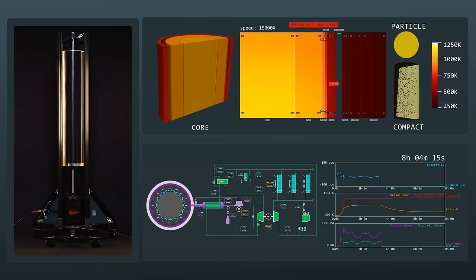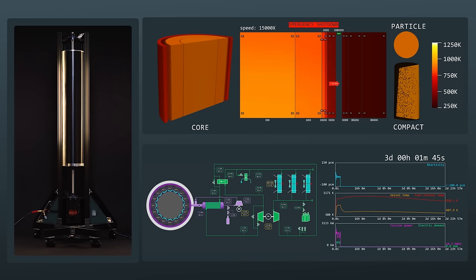A small amount of decay heat is still produced by fission products. After the fuel temperature peaks in a few hours, the entire core cools to ambient temperatures. The fuel never exceeds 950 degrees, well below the 1600 degree limit established by TRISO Fuel Qualification.